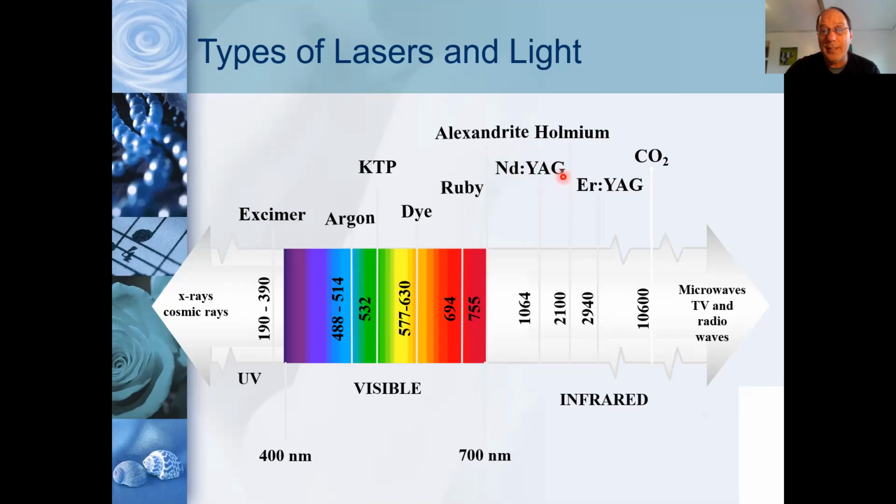And when that garnet is excited and you pull a trigger on it, what comes out of there is a wavelength of 1064 nanometers. So that garnet crystal is what we call a 1064 YAG, and that wavelength at 1064 nanometers is attracted to hemoglobin. We use that frequently for vascular blemishes, for telangiectasias, for cherry angiomas, etc.